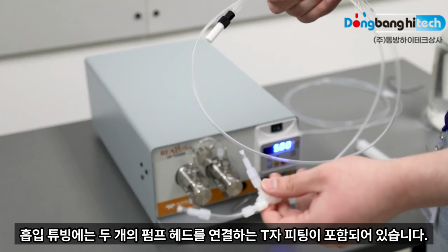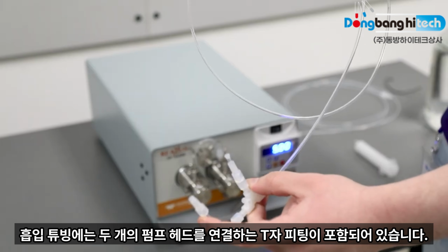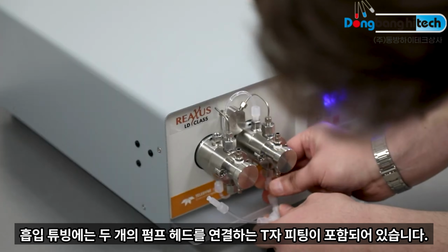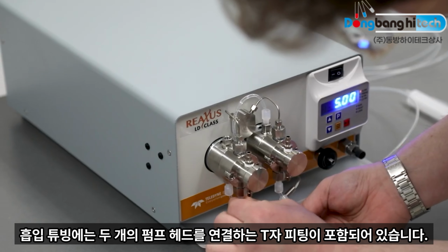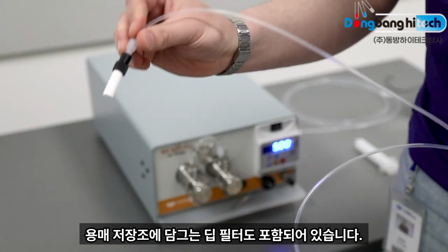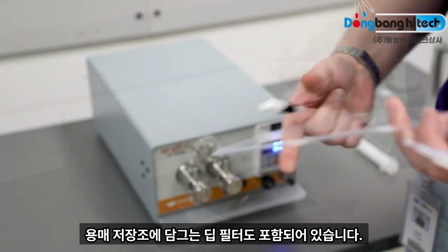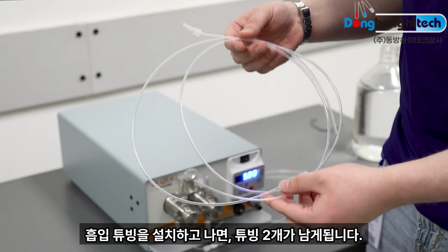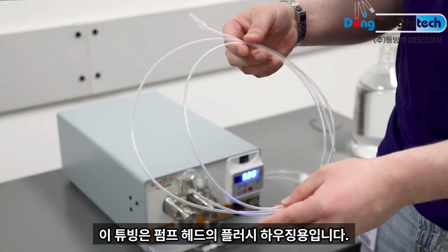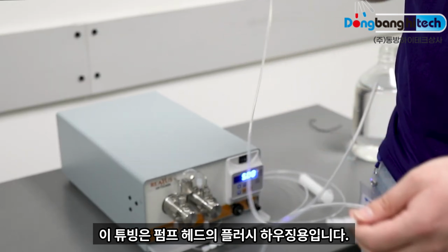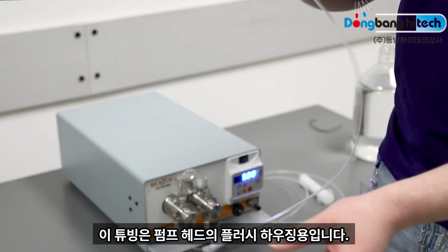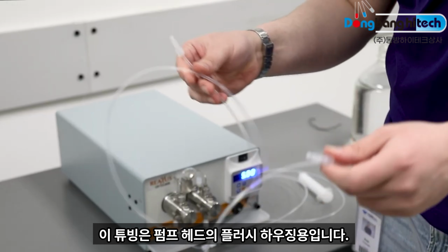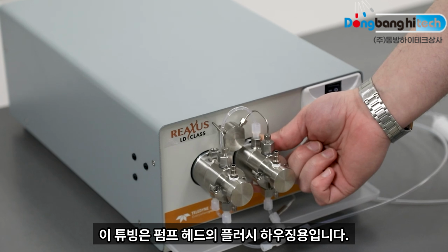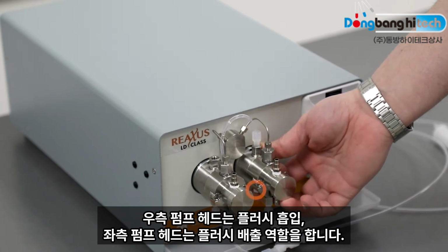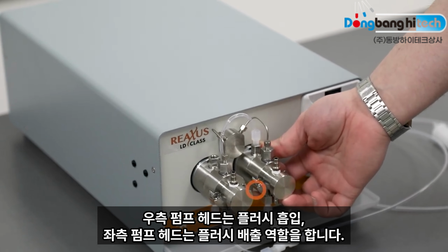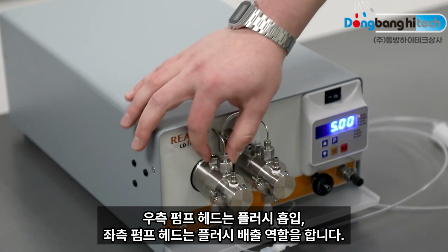Now for the tubing. So for the inlet tubing, it'll include a T that will connect to both of our pump heads, along with a filter, dip filter for our solvent reservoir. Now that the inlet tubing is installed, I will also have an additional 2 pieces of tubing that are unterminated at the ends. These will be for our flush housings on our pump heads. We'll have an inlet for our flush housing on the right pump head for our dual reciprocating pumps, and an outlet on the left pump head.